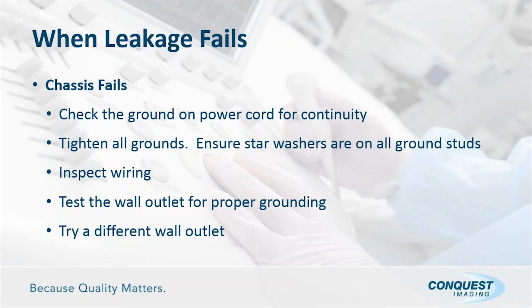If at this point the chassis is failing leakage and you've checked everything that's obvious, check the wall outlet. And if you can't do that because it's not in your purview, since in some hospitals it has to be a facilities person, it should be tested no matter what. One way you can do it without worrying about testing that particular outlet is to take the system to a different room, down the hall, somewhere different, and test a different wall outlet on a different circuit and see if that changes your condition at all. If it does, then it's even more likely that the outlet in that particular room is wired incorrectly. So those are some things to check.